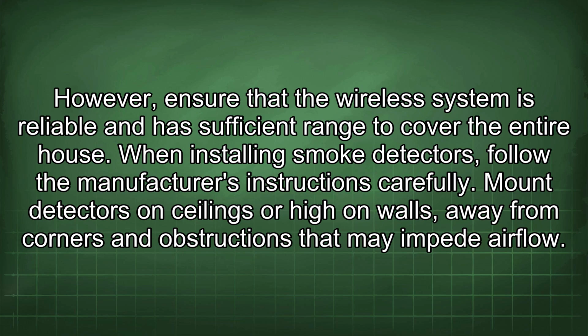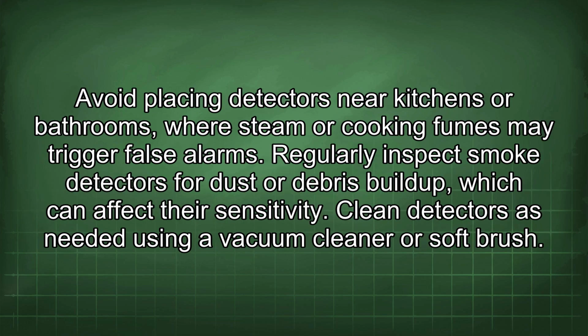When installing smoke detectors, follow the manufacturer's instructions carefully. Mount detectors on ceilings or high on walls, away from corners and obstructions that may impede airflow. Avoid placing detectors near kitchens or bathrooms, where steam or cooking fumes may trigger false alarms. Regularly inspect smoke detectors for dust or debris buildup, which can affect their sensitivity. Clean detectors as needed using a vacuum cleaner or soft brush.